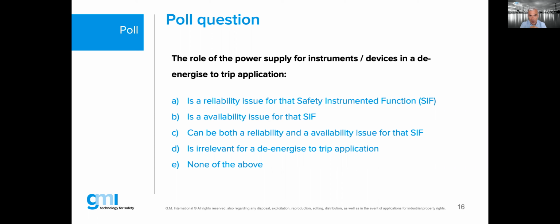Equally, under voltage to some final elements in a certain configuration can also be an issue. So in terms of safety, it is a reliability issue, because if you have a power supply that cannot feed the function it was designed for, it can actually stop your safety functions from achieving their purpose. And this is also an availability issue. Although we speak about de-energize to trip, it can be both reliability and availability. Okay, I will stop sharing and I will try to explain a bit more in detail now.